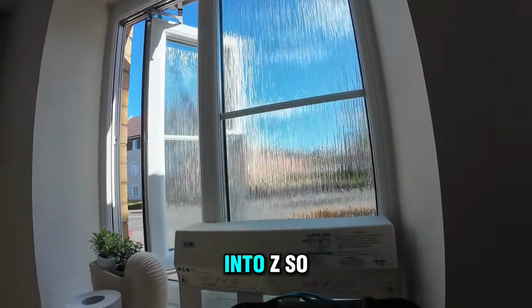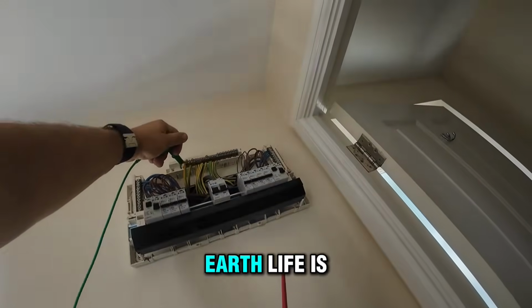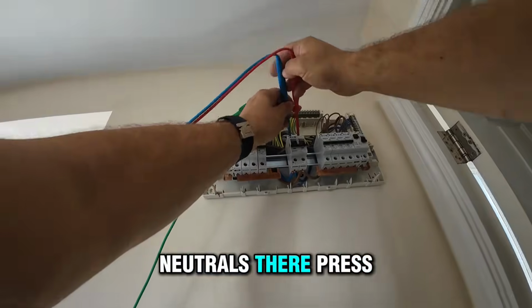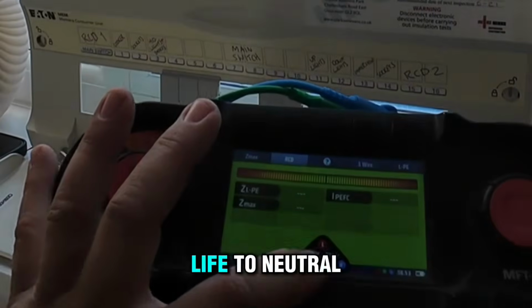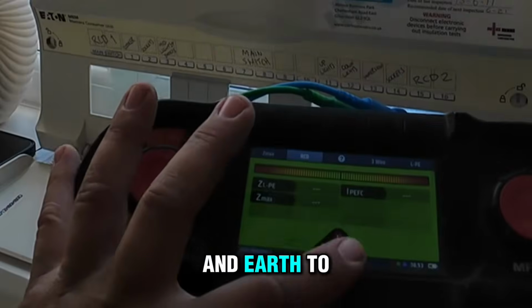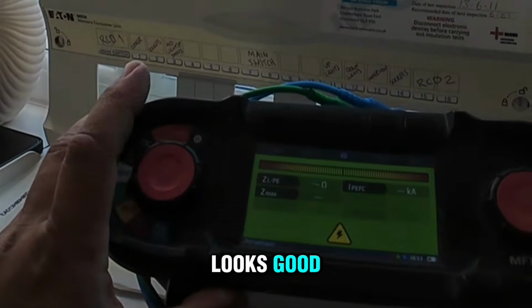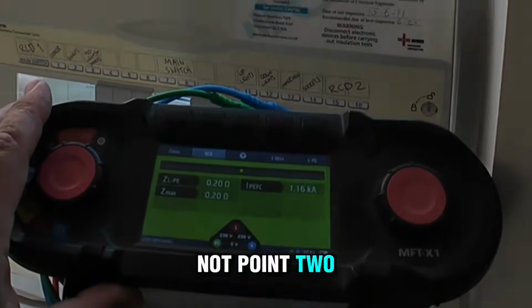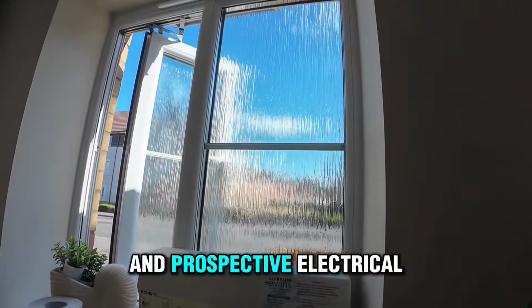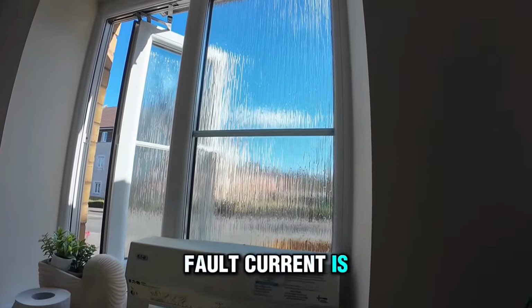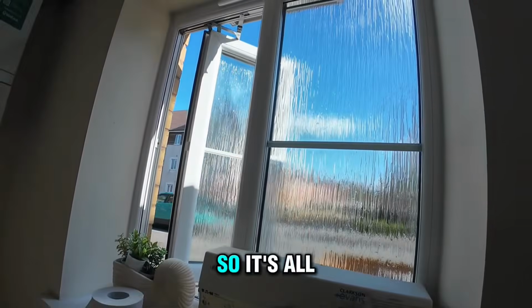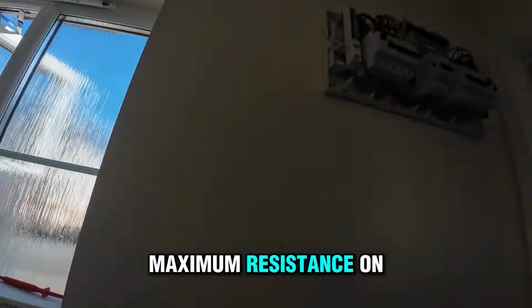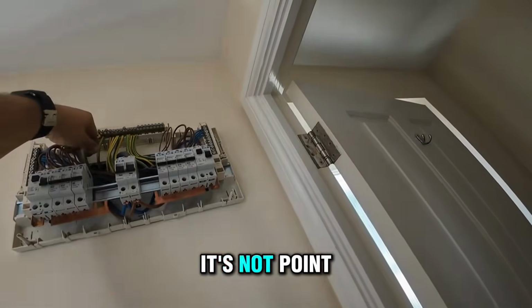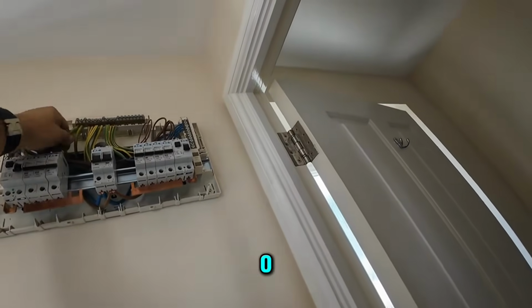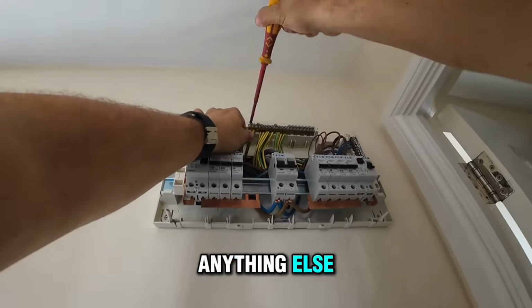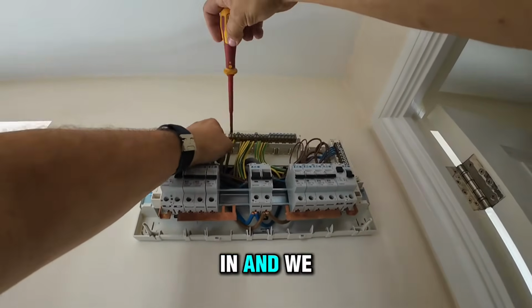Set my tester to Z. So clamping on the earth, live is here, neutral's there. Press to test: 230, live to neutral, live to earth, and earth to neutral 0. So it looks good. 0.20, that's really nice, and prospective fault current is 1.16 kiloamps, so it's all looking good. The maximum resistance on TN-C-S earthing is 0.35, and this one's 0.20. That's pretty good. Before we do anything else, that cable needs to go back in and we can resume the rest.